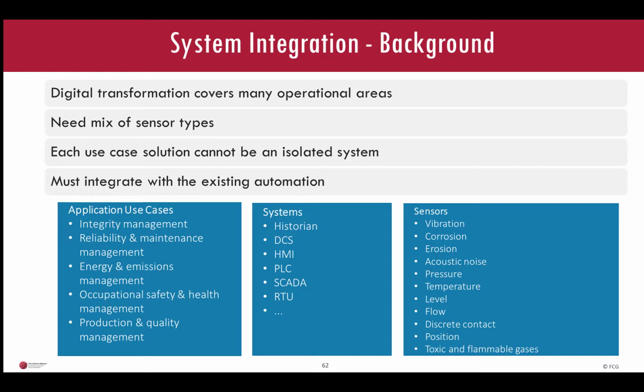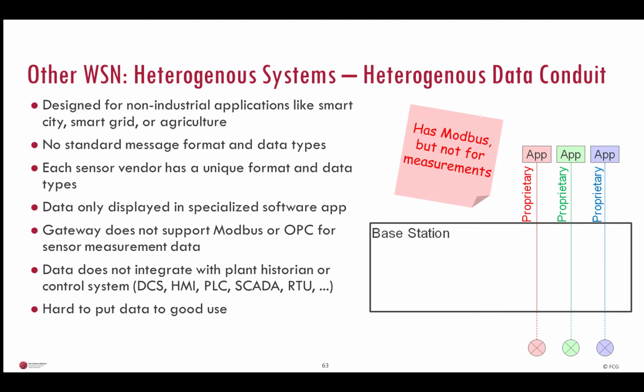Wireless sensors and apps cannot be isolated islands of automation. Sensors and apps must integrate with existing automation, such as the plant historian or control system. Many wireless sensor network technologies were designed for non-industrial applications like smart city or smart grid or agriculture. Such technologies don't define a standard application protocol with a common message format or common data types. Because of this, the gateway does not convert to Modbus or OPC for sensor measurement data. Therefore, sensor data does not integrate with applications like the existing plant historian or control system. This in turn means it becomes hard to put that data to good use, so be careful.